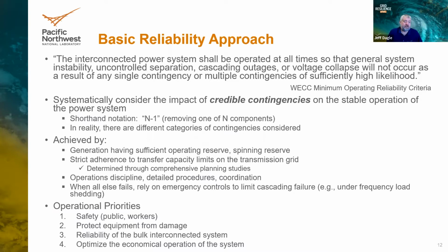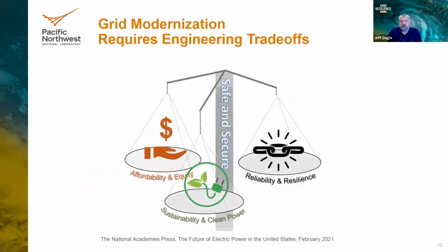When we talk about resilience, the time to restore the system is a very critical aspect. If equipment gets damaged while trying to maintain reliability, that's not a good outcome. Protective relays and protective equipment are designed to trip things offline to protect them from damage, which is the main job of circuit breakers and protection. Then there's maintaining the reliability of the system, and optimizing it to extract as much economic value as possible by trading energy over wide areas.